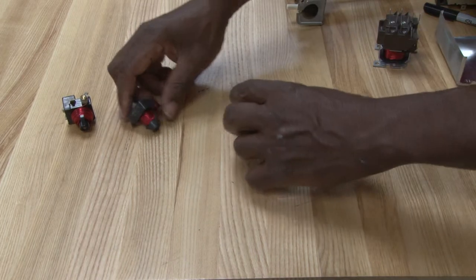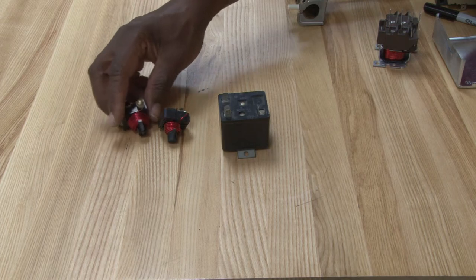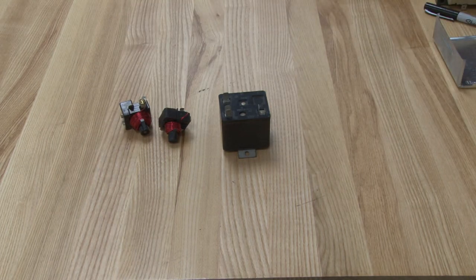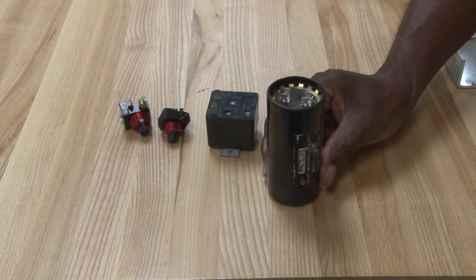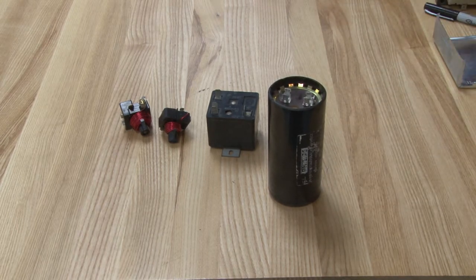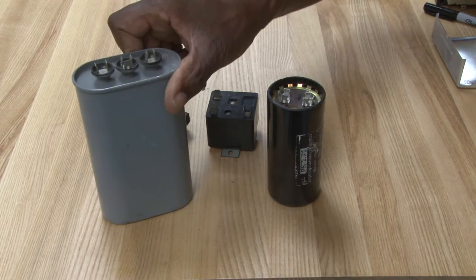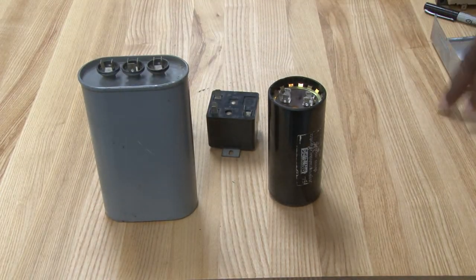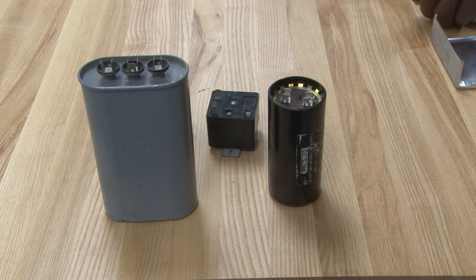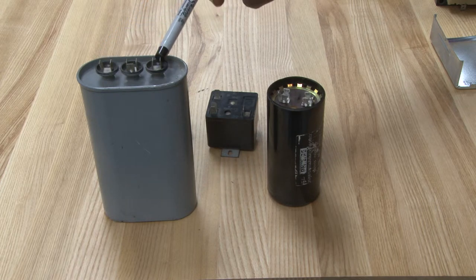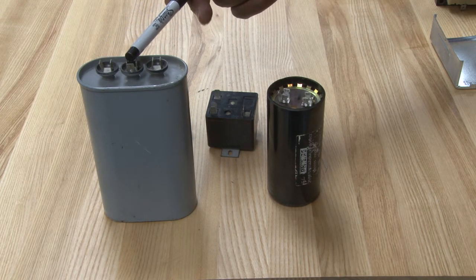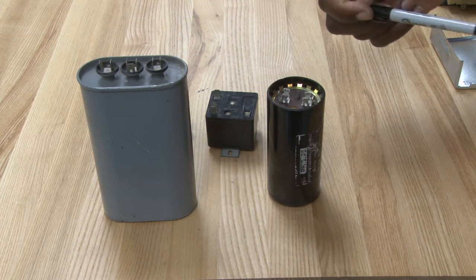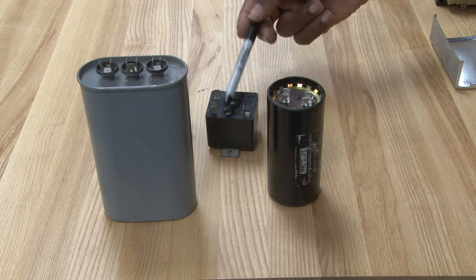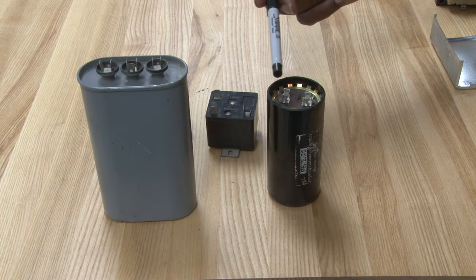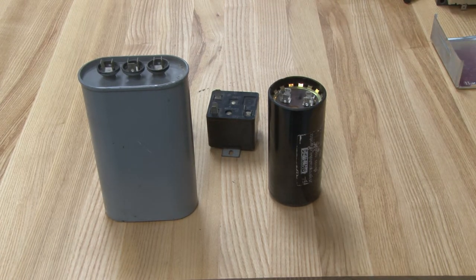Going back to the relays, we have the current relay, we have the potential relay. Those components will take out the start winding, but they will use capacitors. This is the capacitor for the start winding, we call a start capacitor. And here's another one that is a run capacitor. This particular run capacitor is a combination one. It's designed for operating both the compressor and the condenser fan motor. And this is the common coming in, so it splits off to the two different motors. But it'll be used off of a potential relay like this one with a start capacitor to give the compressor more starting torque and running torque.